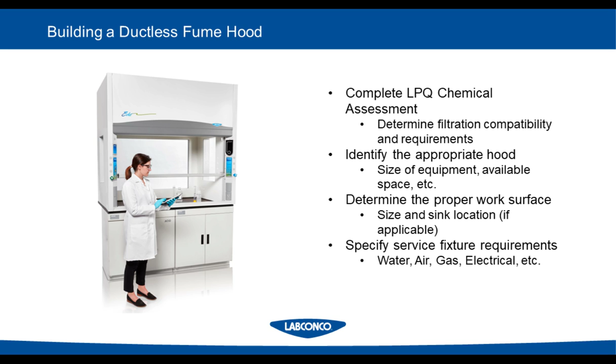Next, most benchtop fume hoods, or all benchtop fume hoods, need somewhere to sit, and that's where a work surface would come in place. Something to take into account would be the size and a sink location if you're using water and need to dispose of it. And then finally, to specify any service fixture requirements that you have, whether that's water, air, gas, electrical, vacuum, pretty much anything that you need to put in your hood, you need to make sure that you're having that accounted for. So that's what we have for the filtered fume hoods in improving your lab's green initiative.